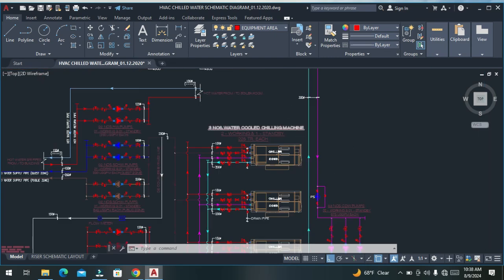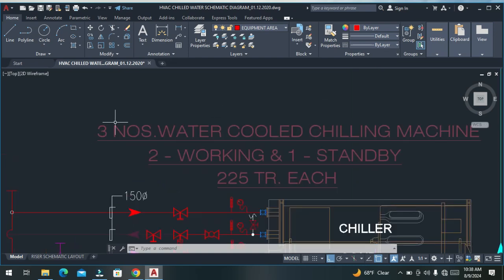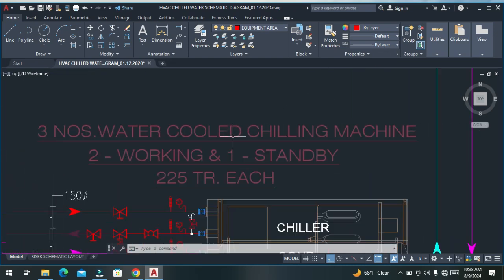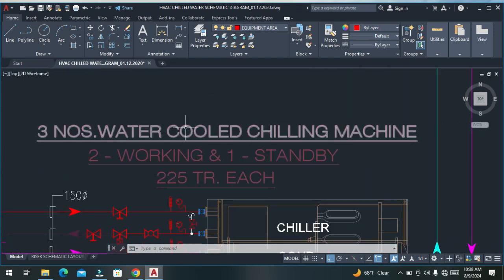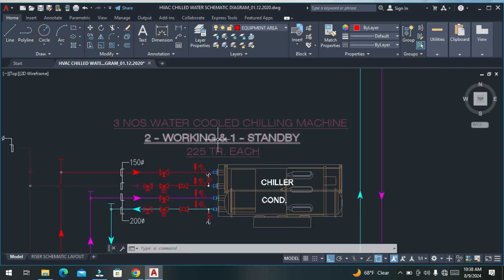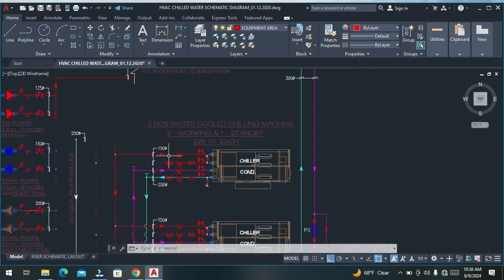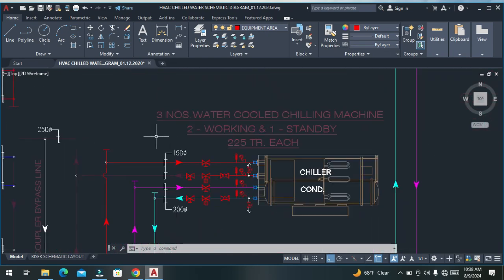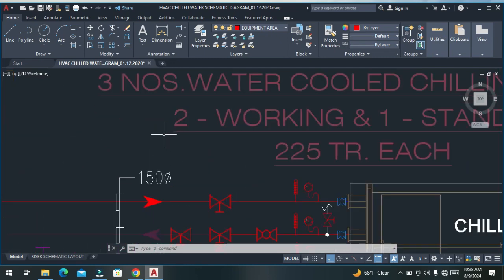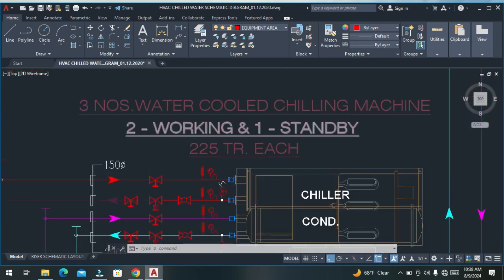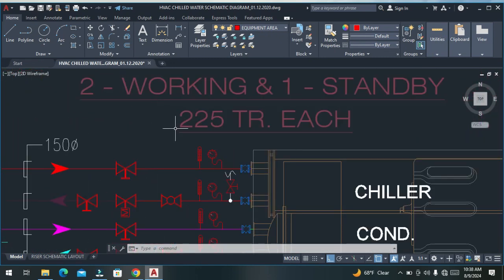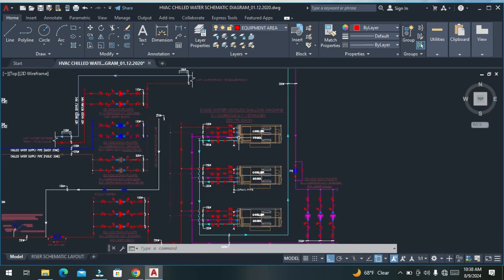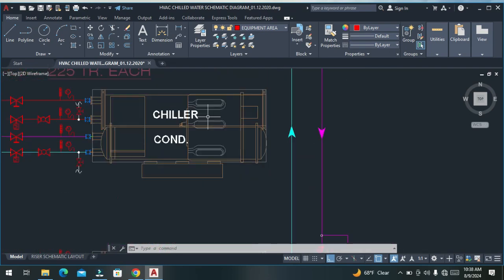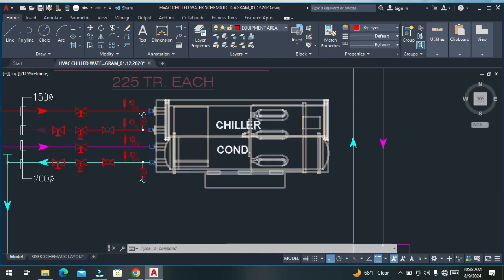As you can see over here, we have three water cooled chilling machines, or we can say chillers. Here the designer has designed it for 2 working and 1 standby. Each chiller capacity is 225 TR, tons of refrigeration. So this is the water cooled chiller.